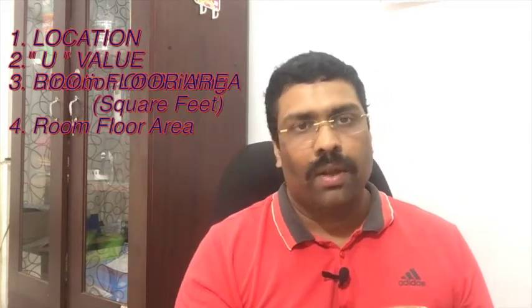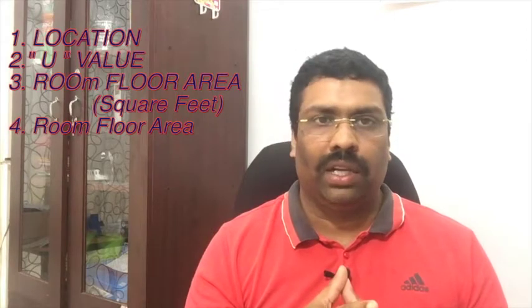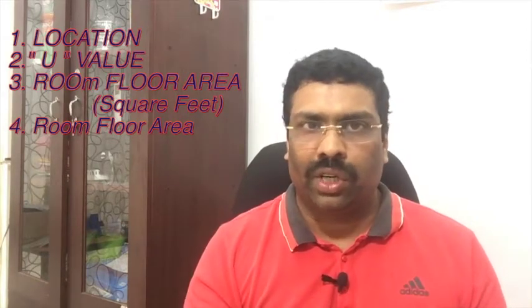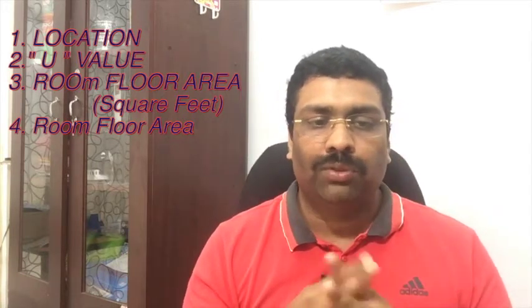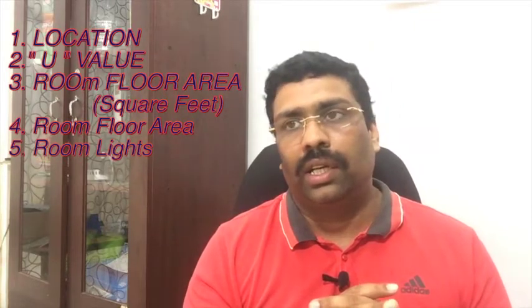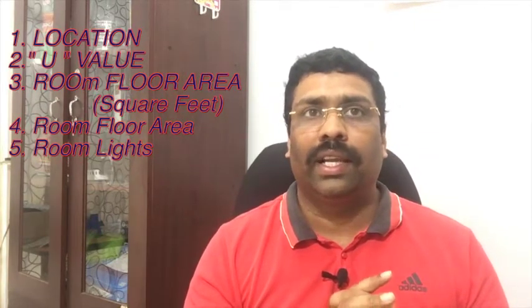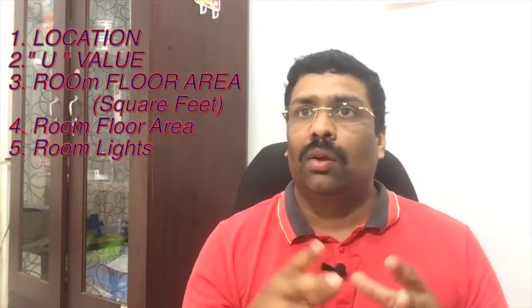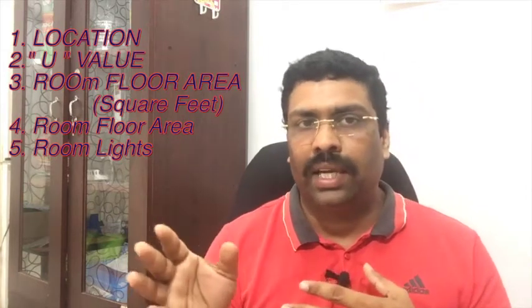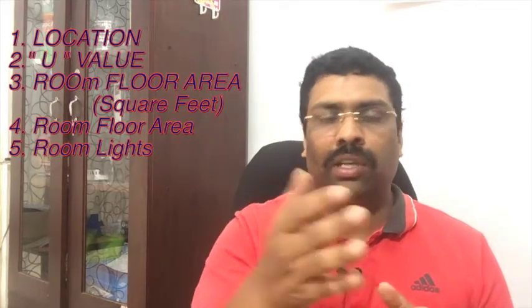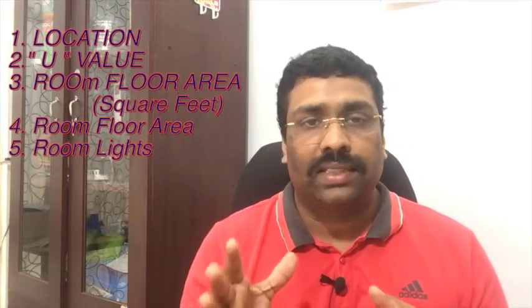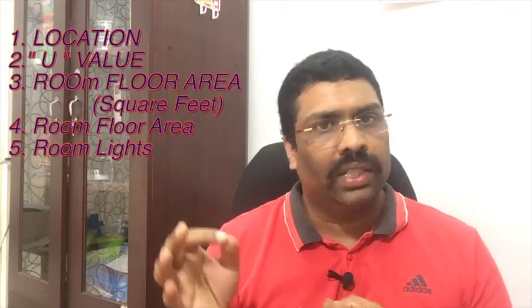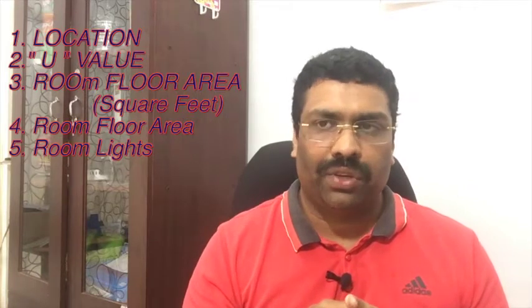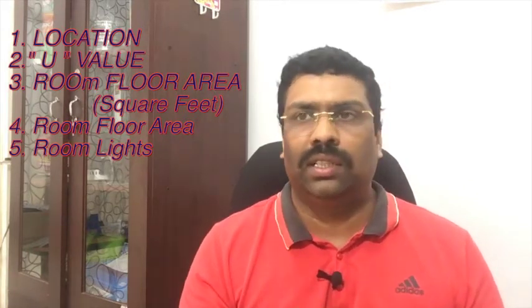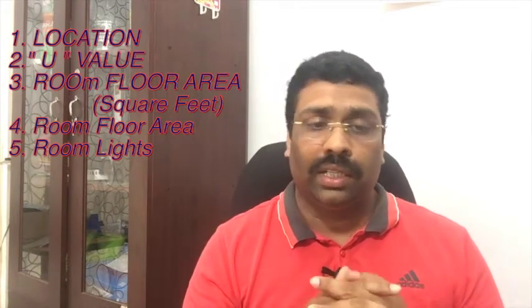The fourth point is room floor area. How many square feet is each room? You can calculate it very simply: length into breadth. If it is in meters, we need to convert into square feet. The fifth point is room lighting: how many lights are in the room, and whether any heat-generating or halogen type lights are there. There is already a standard calculation in HAP, and when I explain the software, I will tell you what it is. For a normal office area, there is a certain number of watts per square foot. We can put that value directly, or we can measure it. It is very simple, nothing big. How many lights we have.